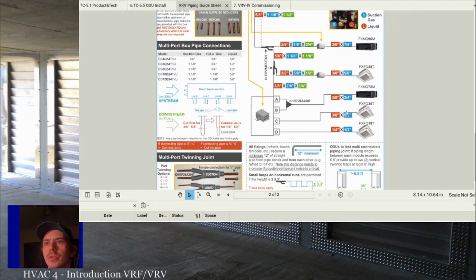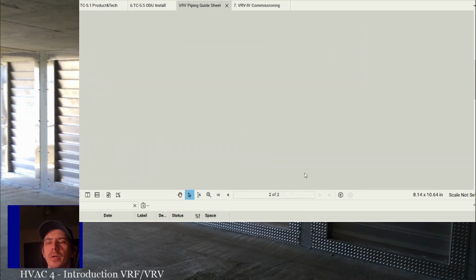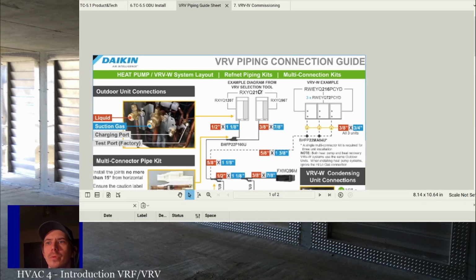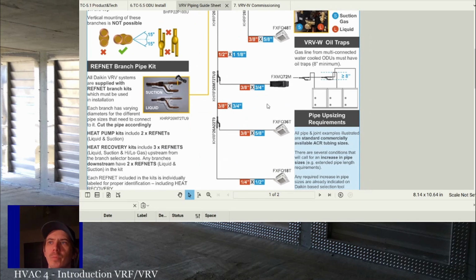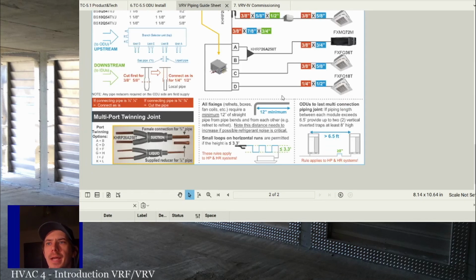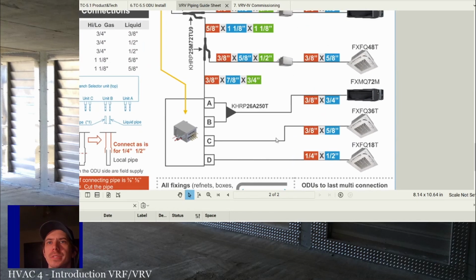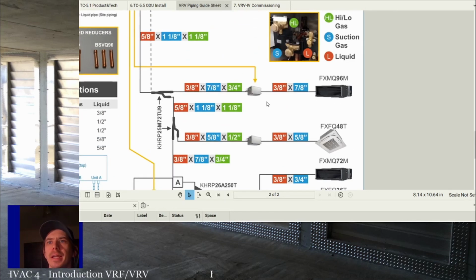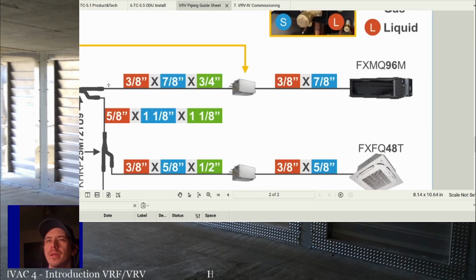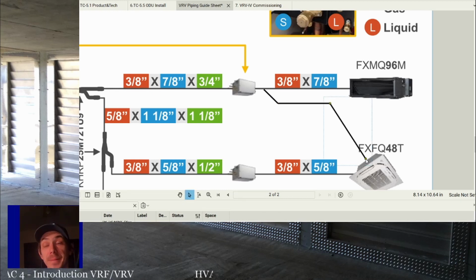The other thing that you can do that they don't show, let me see if they show it on the heat pump. Well, no, because the heat pump doesn't have a branch selector. So the other thing that can happen, and maybe we'll see a diagram of it somewhere else, is you can have this unit go into this branch selector, right? And it can split off after the branch selector with two pipes and serve another indoor unit. What that means is that if both of these units are served off a single branch selector, both of those units have to be running in heating or cooling.